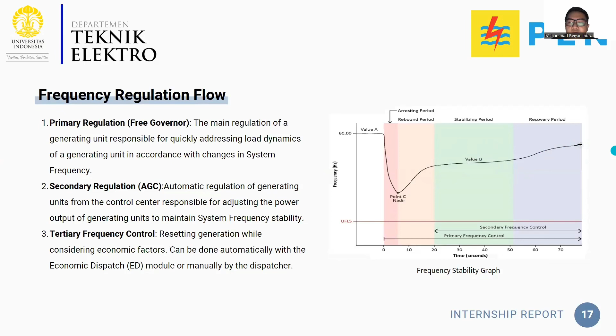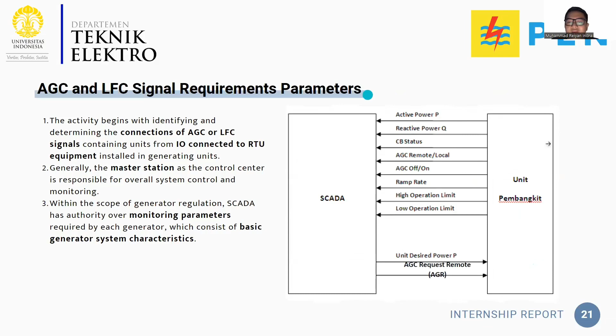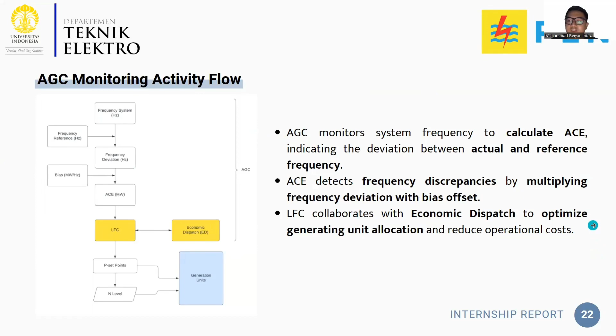This illustration demonstrates how the signal is processed from the generation units to the SCADA systems. Then the SCADA systems will process it and take it as an information system in that computer system. So the next part is the activity of the AGC monitoring flow. This AGC monitors system frequency to calculate ACE, indicating the deviation between the actual and reference frequency. Then the ACE detects the frequency discrepancies by multiplying frequency deviation with the bias offset. Then the LFC collaborates with the economic dispatch to optimize the generating unit allocation and reduce operational costs.